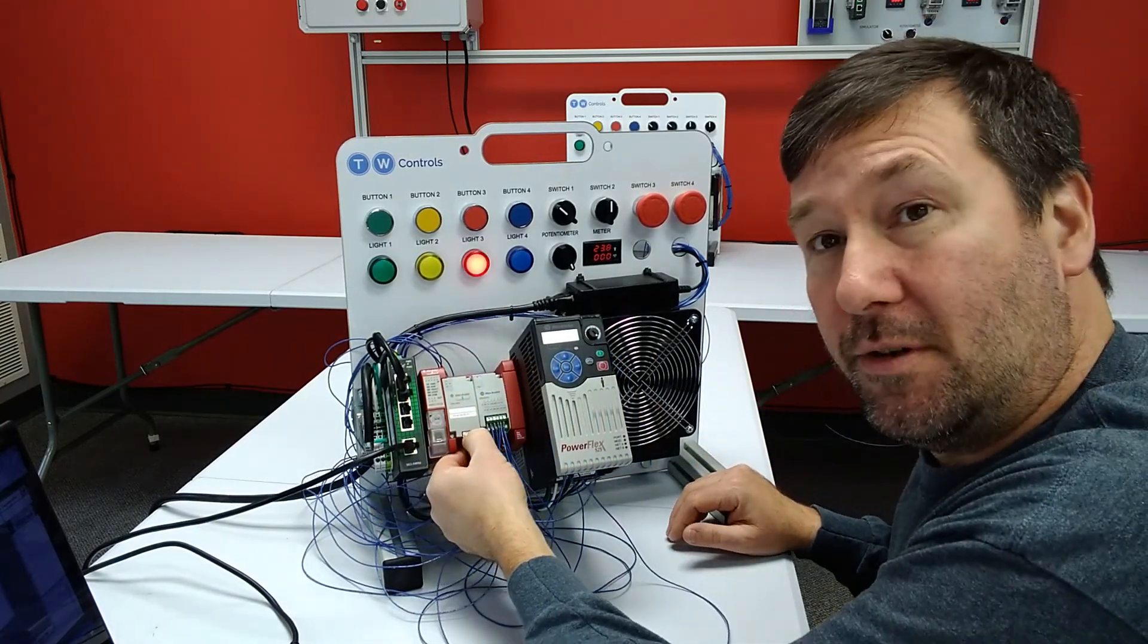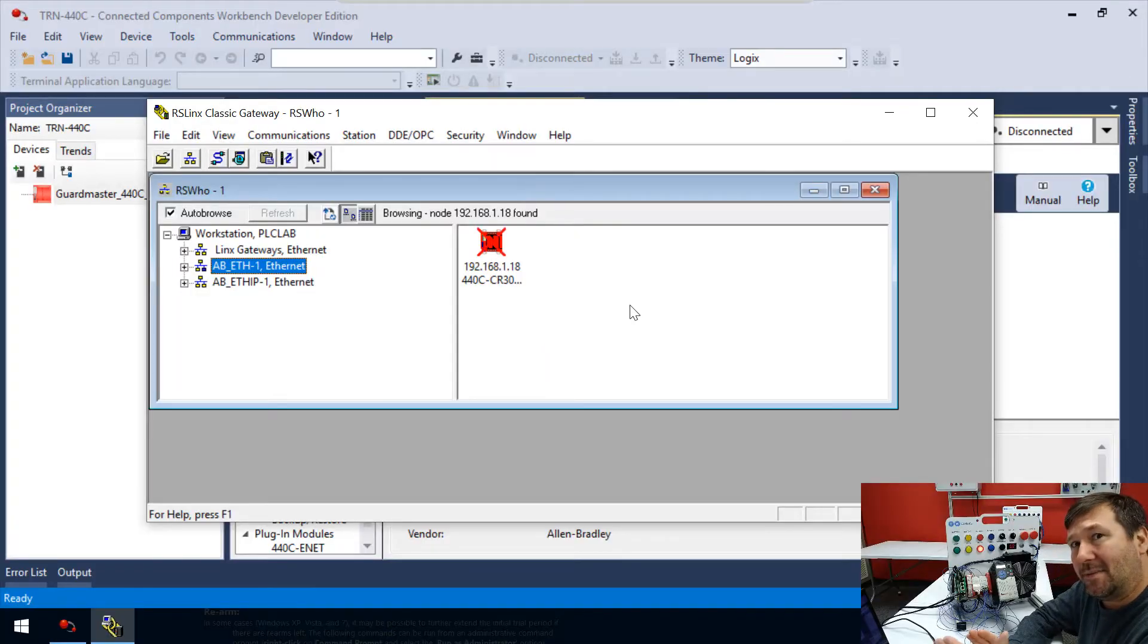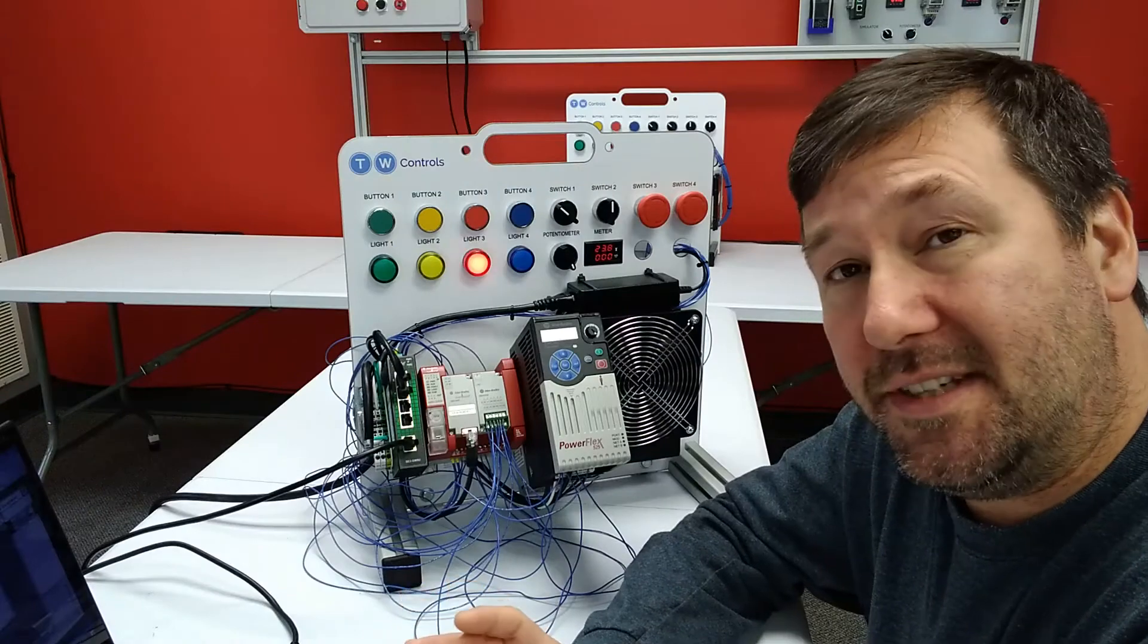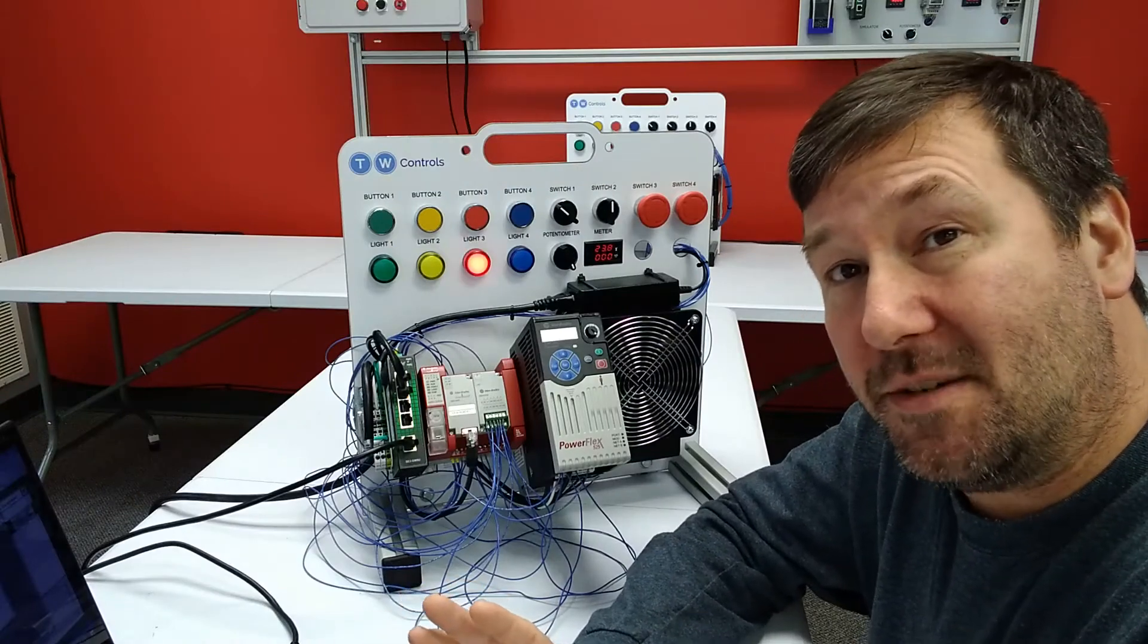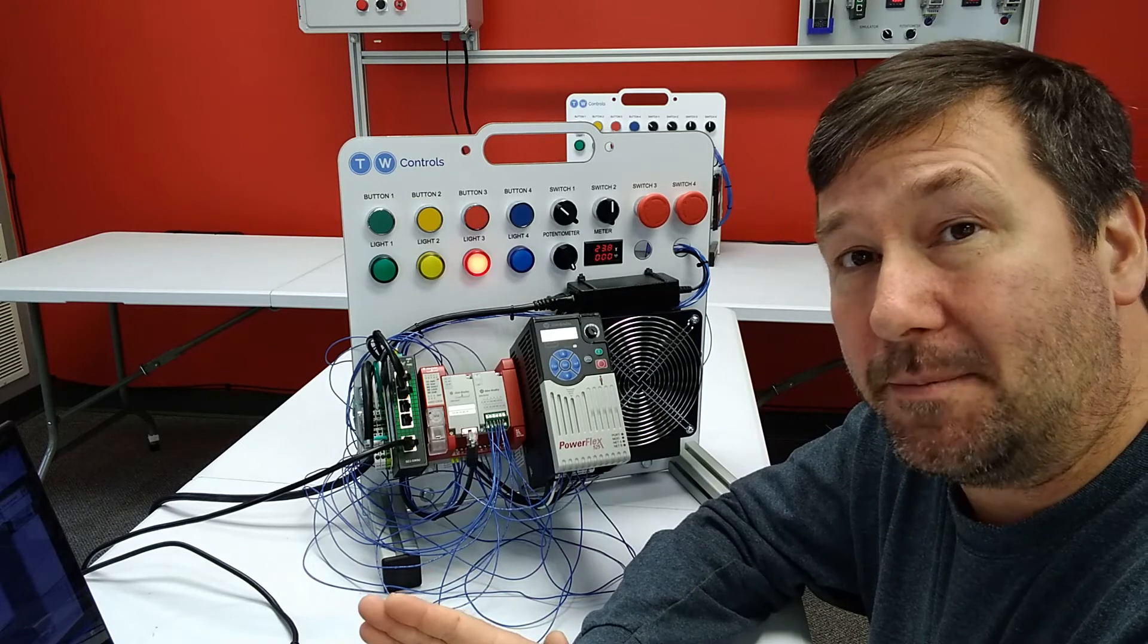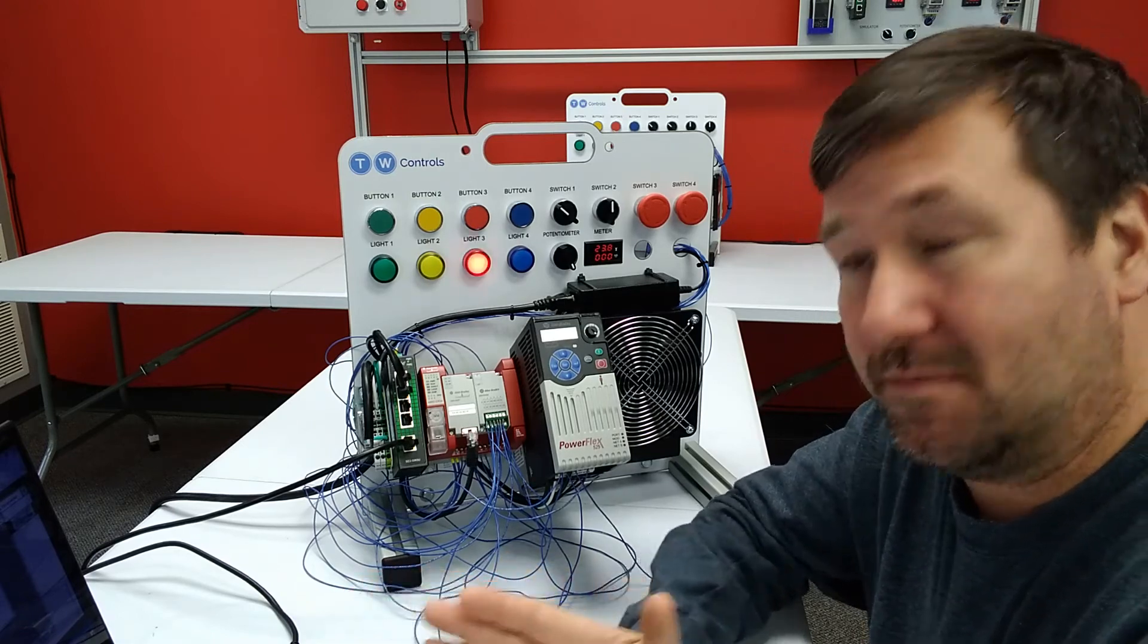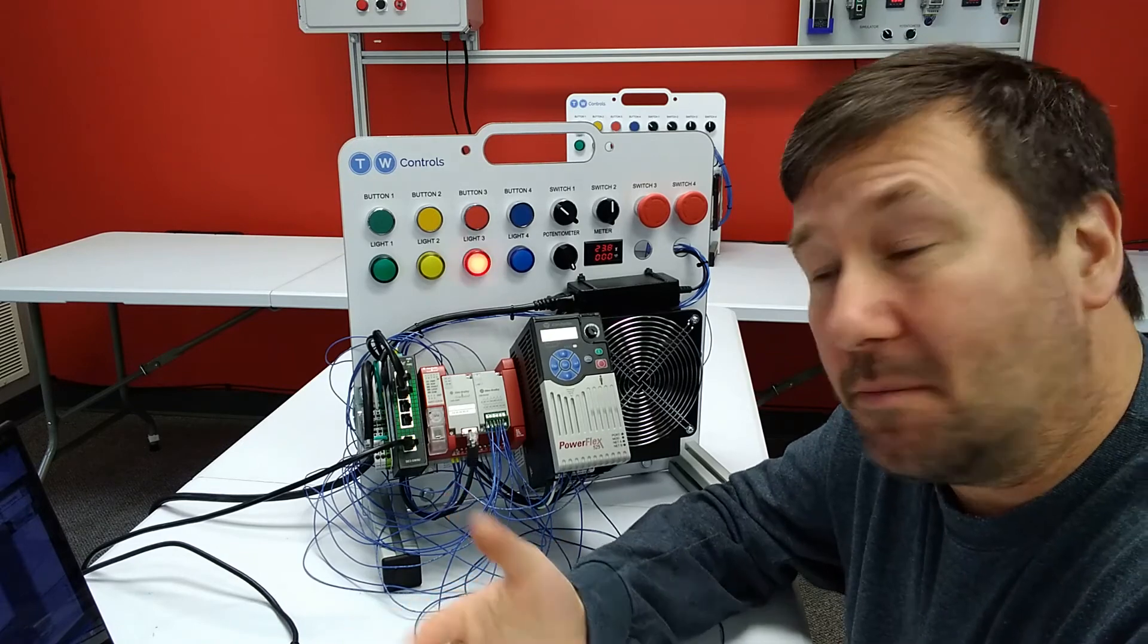We can simulate the red X. Let's just unplug our cord. If we wait a second, now we have a red X. It's a little difficult to see on the CR30, but there is a red X through that PLC now. If you see that, or you see that question mark that I saw initially, you need to stop. Don't try to connect to it in Connected Components Workbench. We've got to work through the problem.